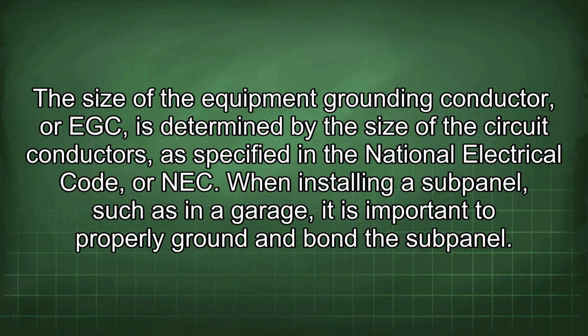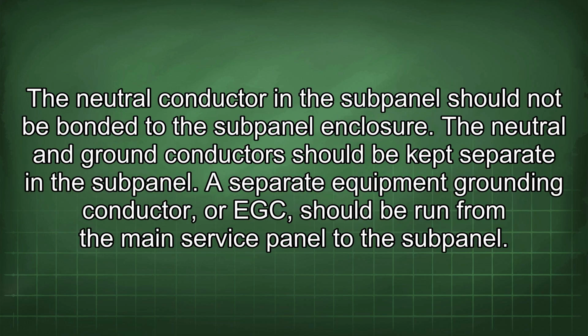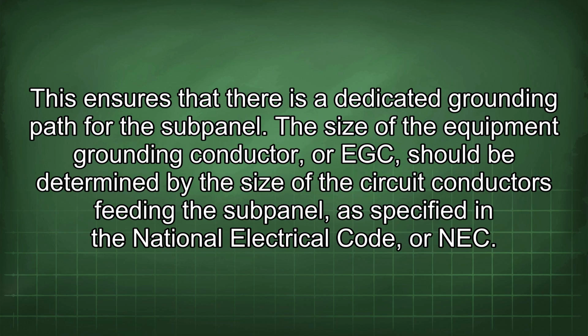When installing a subpanel, such as in a garage, it is important to properly ground and bond the subpanel. The neutral conductor in the subpanel should not be bonded to the subpanel enclosure. The neutral and ground conductors should be kept separate in the subpanel. A separate equipment grounding conductor, or EGC, should be run from the main service panel to the subpanel. This ensures that there is a dedicated grounding path for the subpanel. The size of the EGC should be determined by the size of the circuit conductors feeding the subpanel, as specified in the National Electrical Code, or NEC.